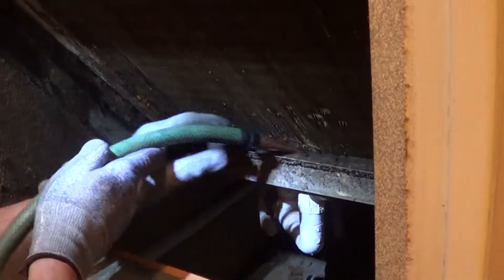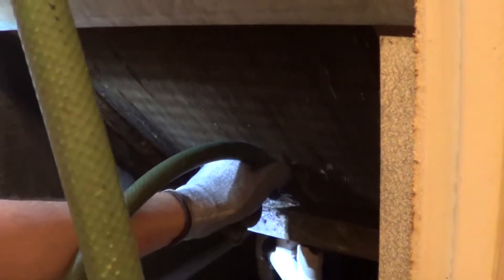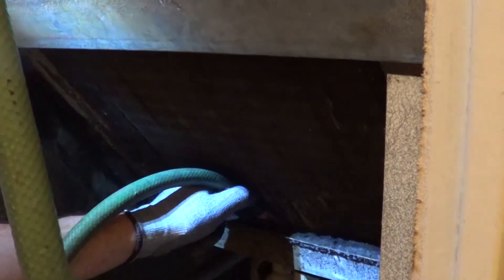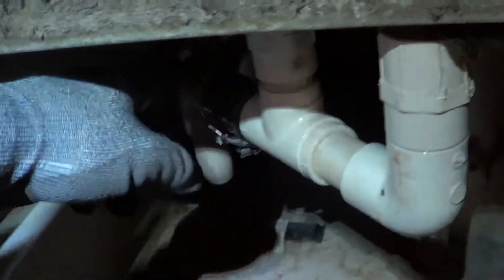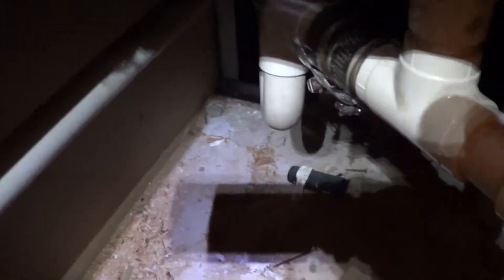Here's a video of what the drain looks like on the primary pan inside the drain. You can hear it gurgle out, and that flushes the drain out. What it did is it went to the source of the drain. It forces the water through the trap. Anything that's in the trap gets pushed out with the pressure, and then it goes out the building.